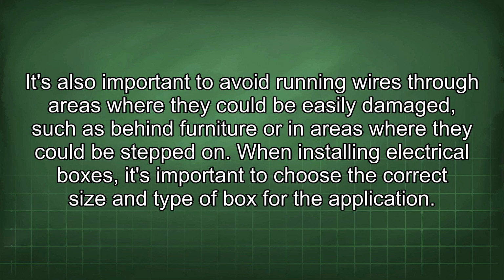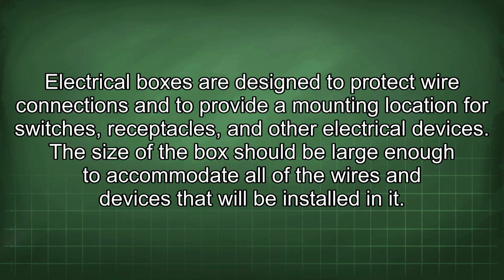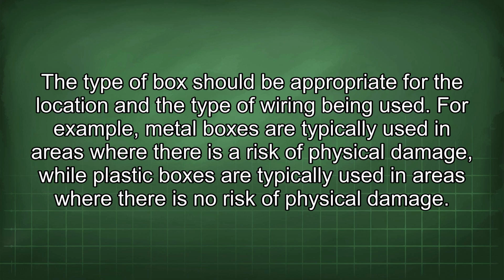When installing electrical boxes, it's important to choose the correct size and type of box for the application. Electrical boxes are designed to protect wire connections and to provide a mounting location for switches, receptacles, and other electrical devices. The size of the box should be large enough to accommodate all of the wires and devices that will be installed in it. The type of box should be appropriate for the location and the type of wiring being used. For example, metal boxes are typically used in areas where there is a risk of physical damage, while plastic boxes are typically used in areas where there is no risk of physical damage.